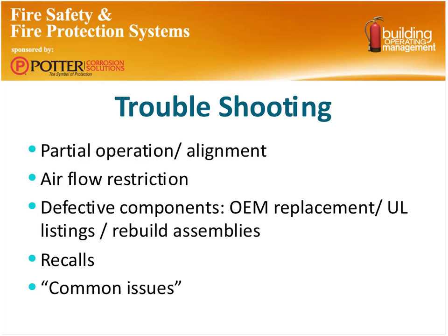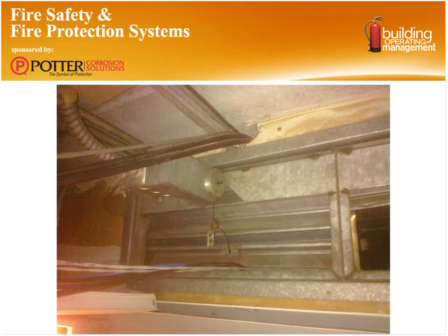So with that in mind, in some cases there are times when a unit just has to physically be replaced. It can't be rebuilt. There are some issues sometimes with recalls. Back in the 90s, there was a big issue with some of the motors seizing up, and that was due to the grease inside the units not having been functionally tested. The grease had dried out because the motor kind of gets hot, and over time that grease became packed and tight and didn't allow that gear set to operate. So those are typical problems that we see in the field. I'll run through a few pictures here just so you can see what it is we're talking about.